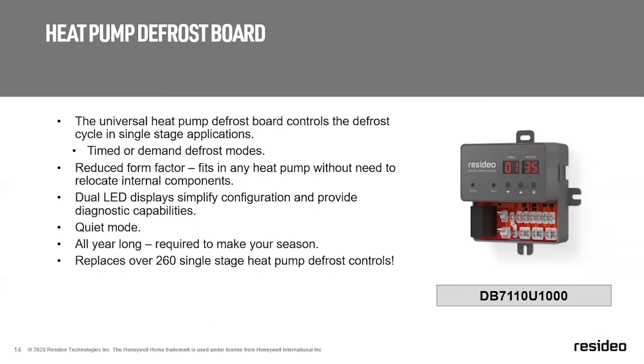Another board that Resideo just came out with in the last year or two is the Universal Heat Pump Defrost board. This is really exciting because it replaces over 260 single-stage heat pump defrost controls. So if you are working on heat pumps, I suggest you put one or two of these on your truck. The reason being, it's a small square footprint and it's really easy to program. It's got two dual-digit LEDs, so you can program this device. It also has a quiet mode, so when you transition to defrost, it's not as loud.